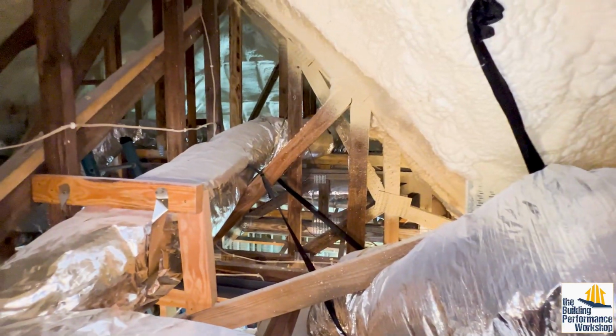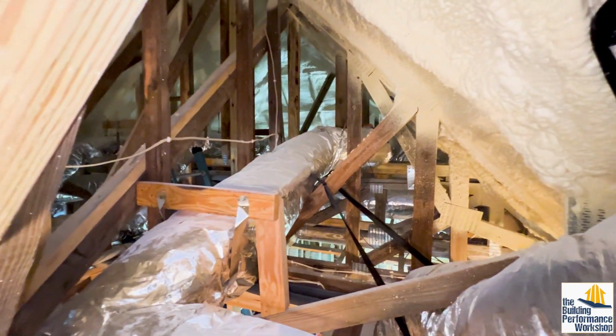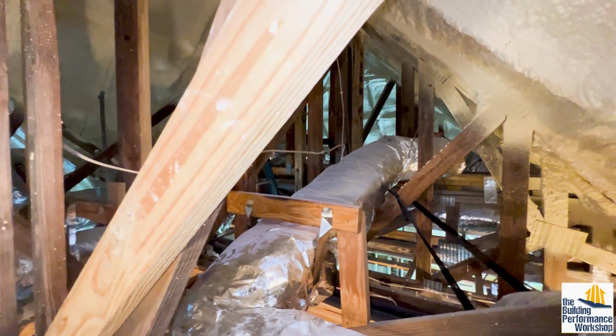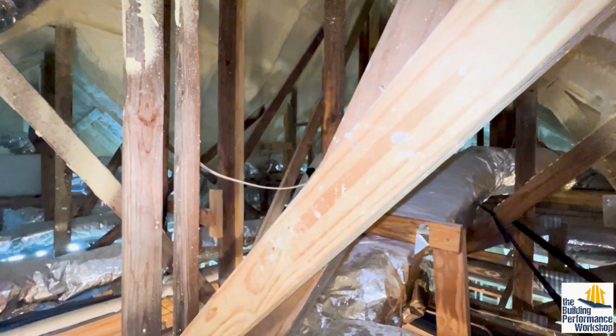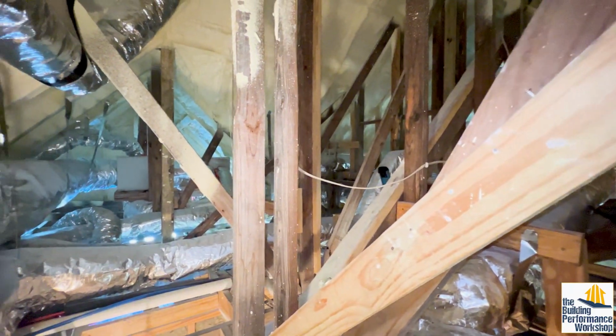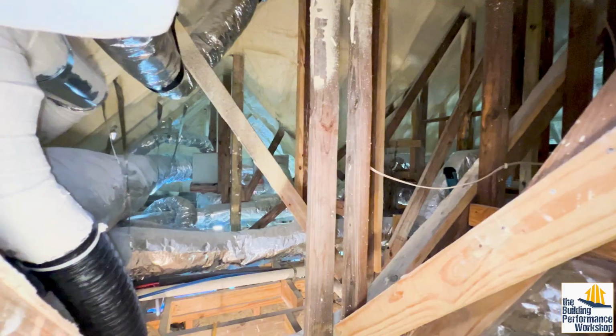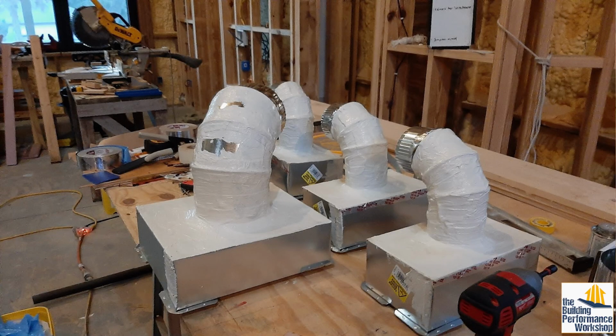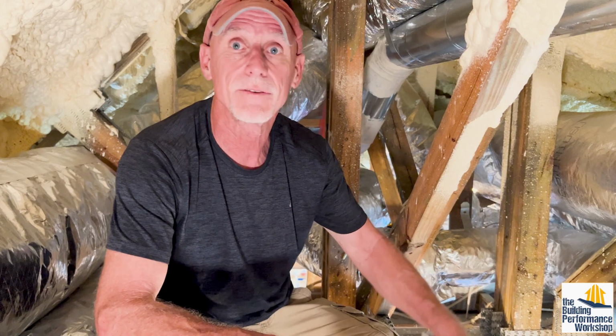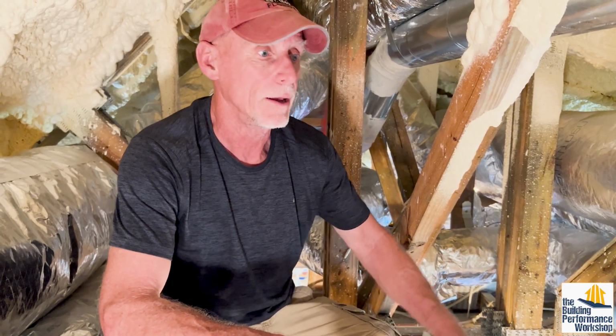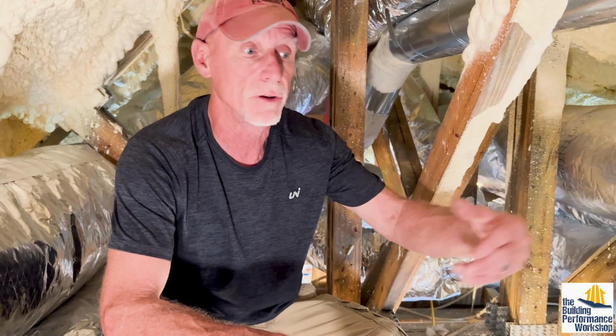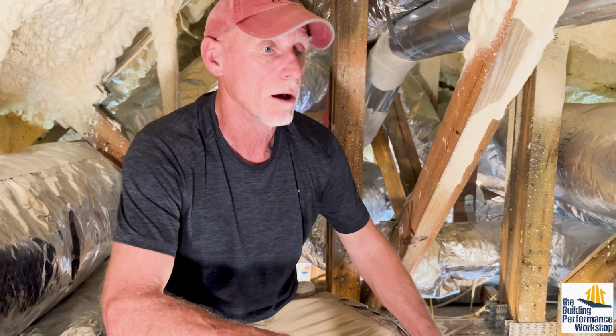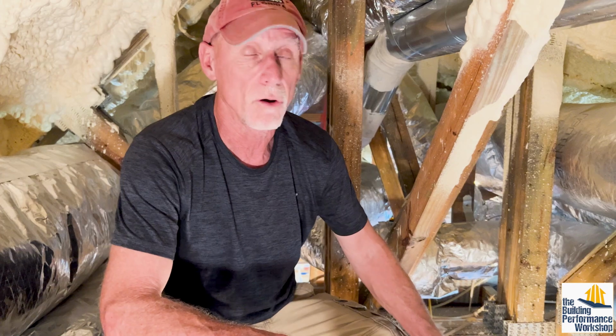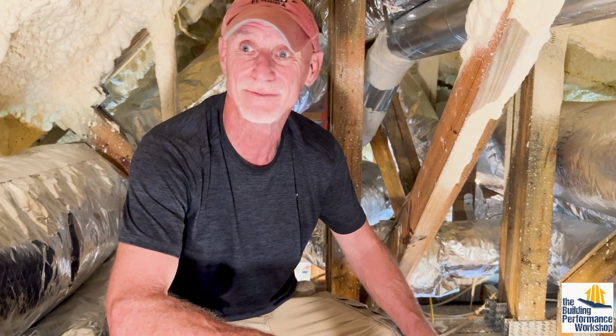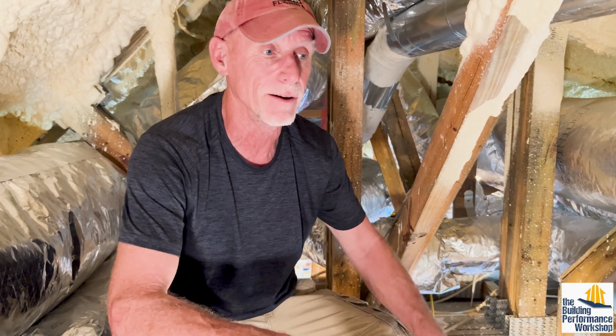These all weave around the truss. There's another problem with trusses: there's not an easy place to run ductwork, so you have to maneuver around the truss work. They build the trusses to support the load, not to support the duct system. So that's kind of interesting here, mapping it out and trying to get it through. Most of the ductwork is 12-inch, there's some 14-inch in here, but there's not a lot of 12-inch holes in the trusses in this complicated assembly.